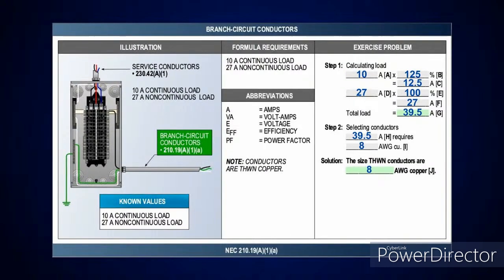I'm going to do a branch circuit next. I've got 10 amps of continuous, 27 amps of non-continuous. So 10 amps times 125% is 12.5. Add the 27 to it, 39.5 amps. The next size above that in the 75 degrees C column is number 8, which is good for 50 amps. Now, was that hard? No, it was simple, and I didn't change that calculation one bit.